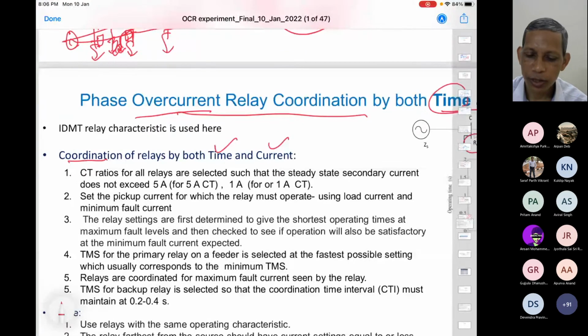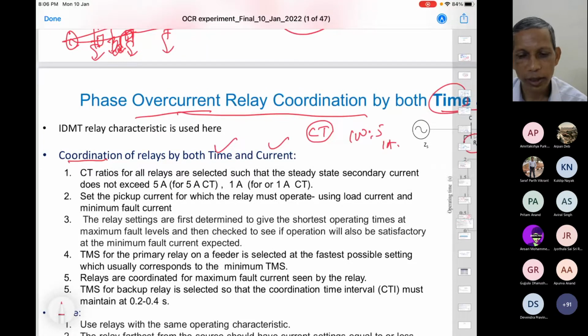So first is the selection of the CT. 100:5 or 100:1. These are the standard ratios. 1000:1, 400:1, 200, 300:1, and so on. How do you decide that? You have the rated current or maximum current of the system, which you know. That is the guideline for whether I take 100 or 200 or 1000. Once again, based on your load current, you decide this side.